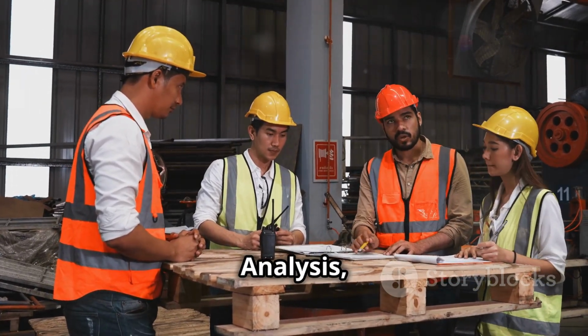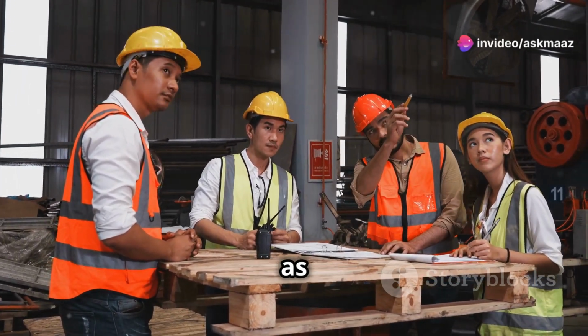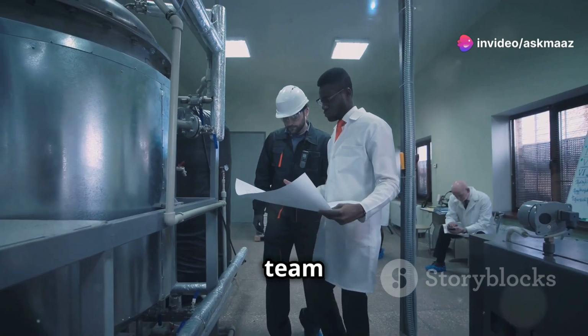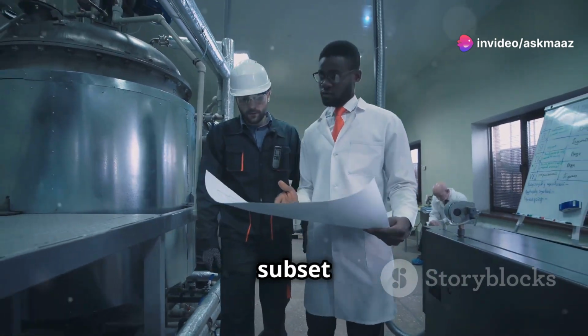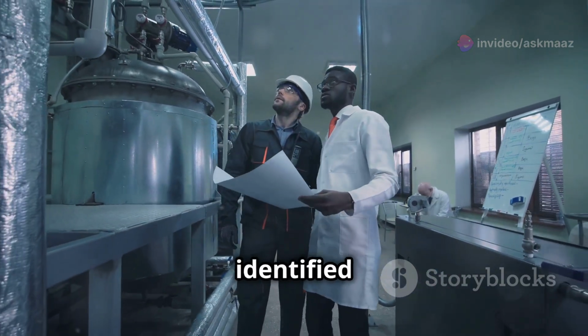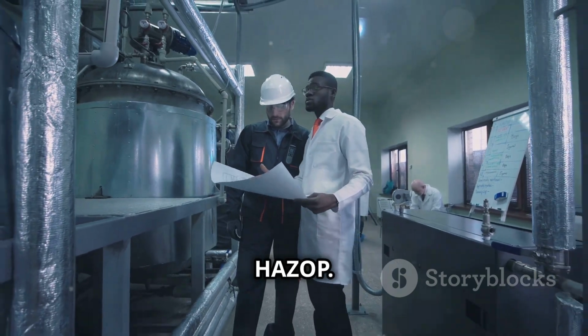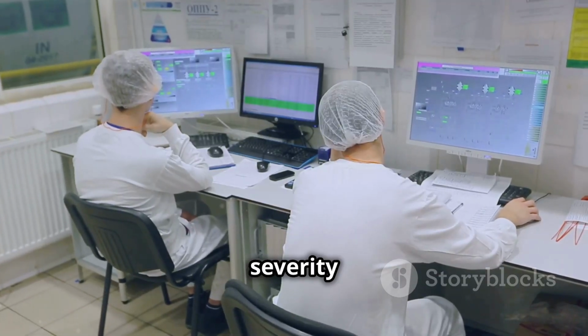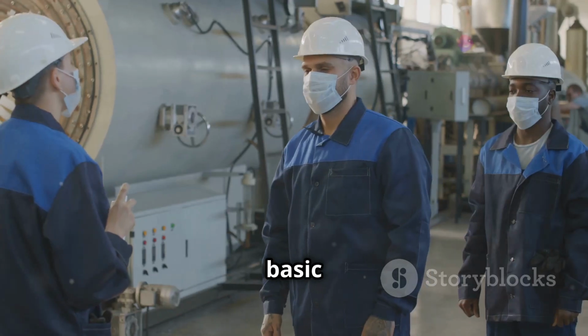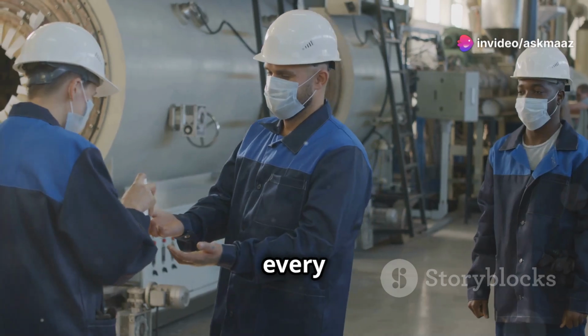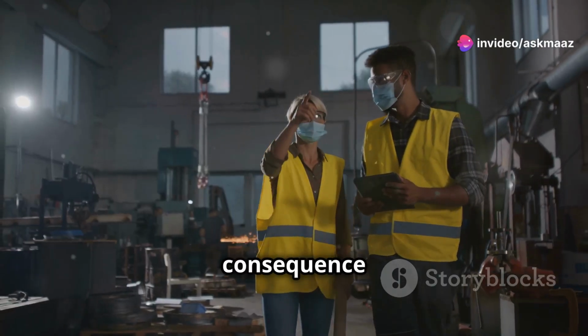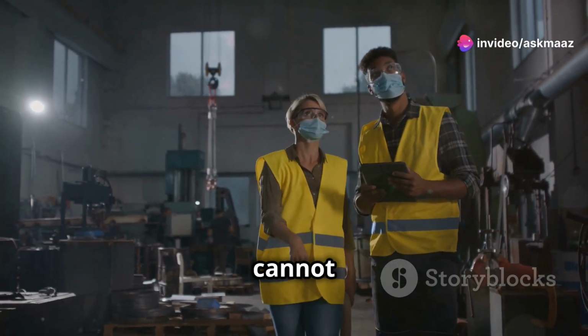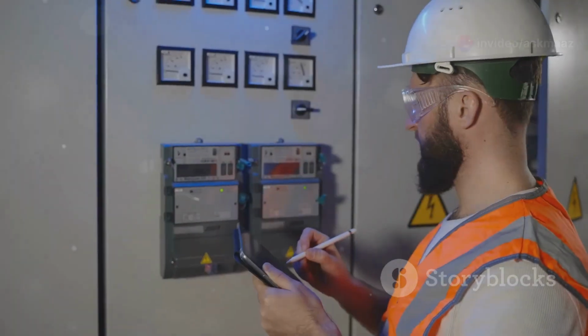Layer of protection analysis, commonly known as LOPA, is where a small team further analyzes a subset of the most hazardous scenarios identified during a HAZOP. They assess the frequency and severity of the consequence. The basic principle of LOPA is that every safeguard may fail, so the consequence of the non-protected scenario cannot be eliminated.